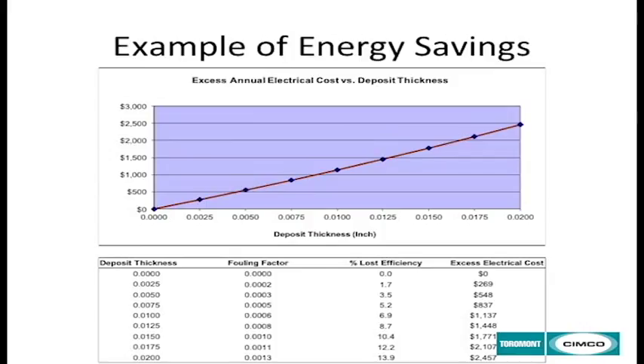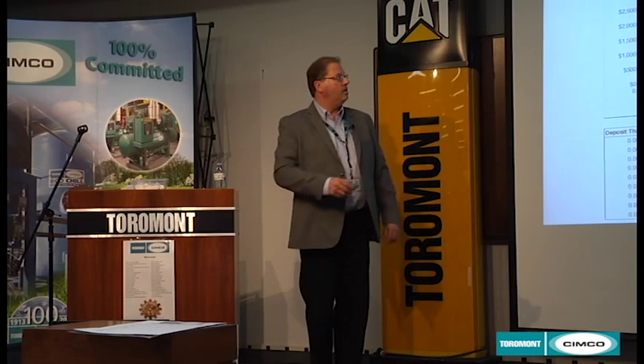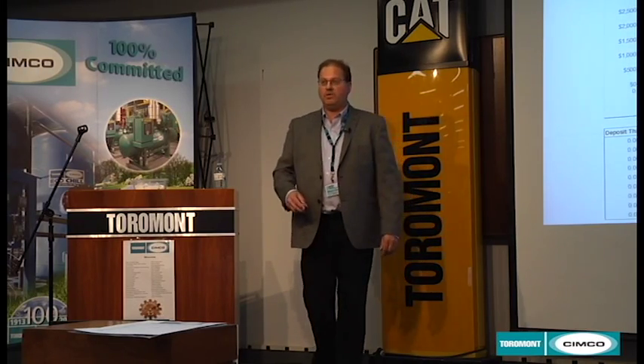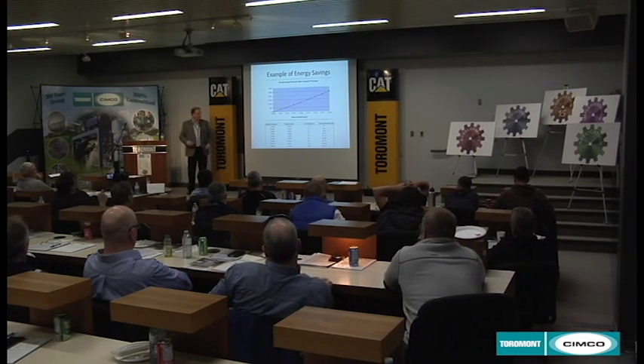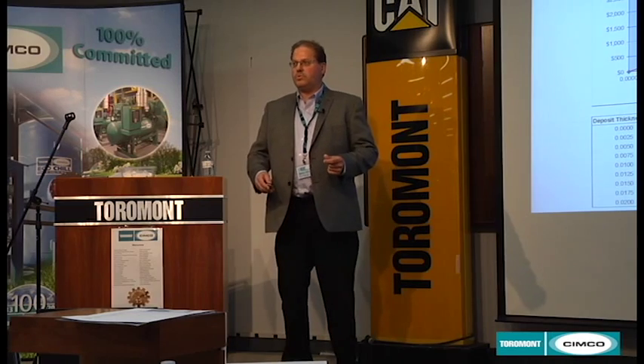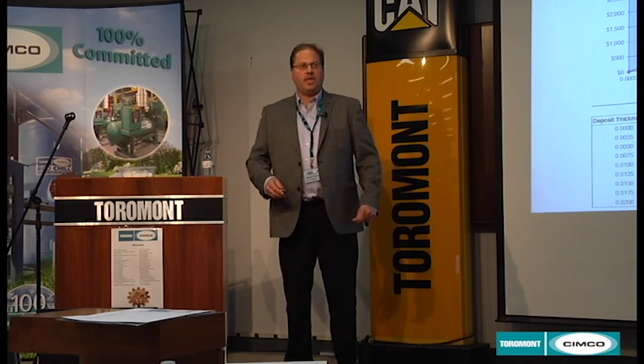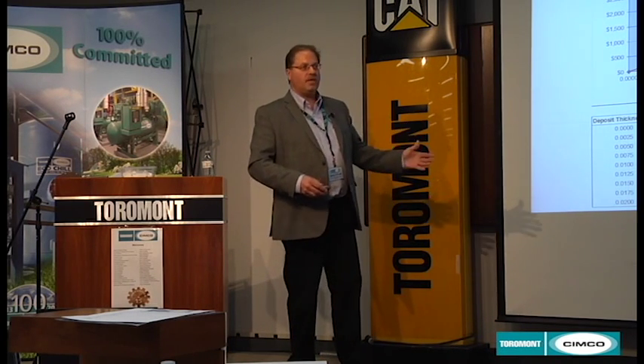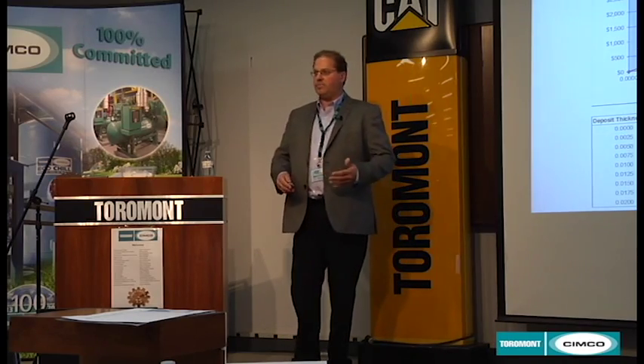Energy costs. Very realistic value of cost associated with the thickness of scale. This is the same 150-ton cooling tower operating 24 hours, 180 days a year. If you had 0.0025 or 0.005, I brought it up to 0.02. You see, 0.02 is not very thick. It's very thin. And you could start using $2,500 more in energy with that small thickness of scale. That's a 150-ton cooling tower. So any kind of thickness of scale on your condenser tubes will increase energy costs. Consider that. Water treatment will help you minimize that cost, help you conserve that scale deposition potential.